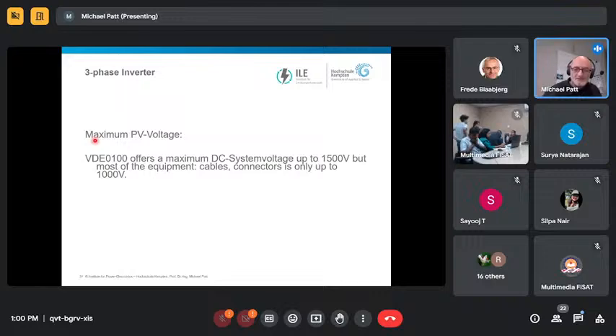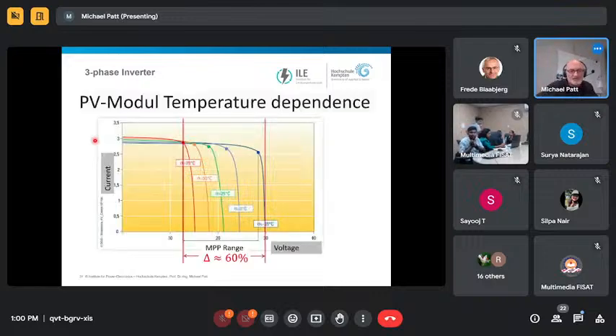So what is the problem here? Let's take a look at the PV module curves. They are very temperature dependent. In this picture we have the same radiation but different temperatures. The output voltage of my module, or my MPP voltage, depends highly on temperature. In Germany, especially in the south, we have to calculate with minus 25 degrees. And this is the open circuit voltage.